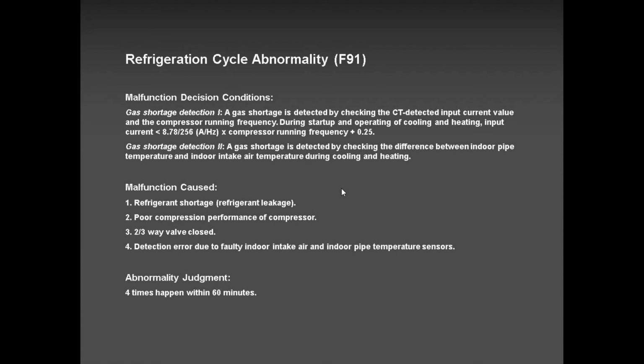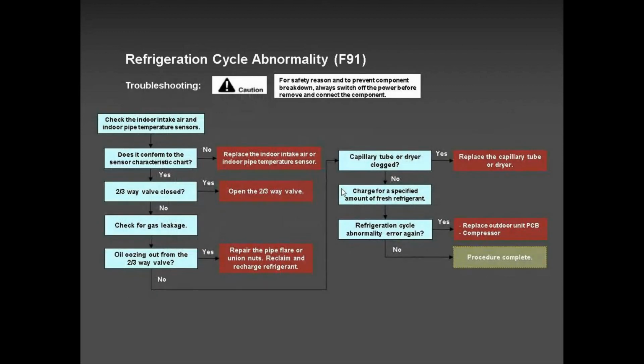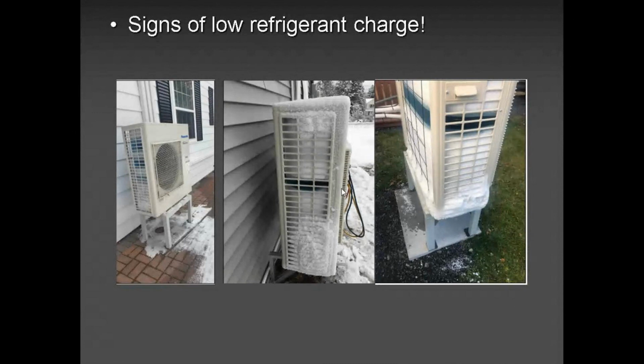F91, if you get an F91, definitely 99.9% number one is refrigerant shortage. Now you could be having a leak or the system is low on refrigerant. Now how low? Again, I'm not blaming the installer. Maybe it came from the factory. Very rare, because the factory tells me, and I've been there and seen it with my own eyes, they weigh each and every outdoor unit that comes off the conveyor belt. If it's off by a few micro ounces, the unit is kept aside as a defect, and it will tell you what the defect is, low refrigerant charge.